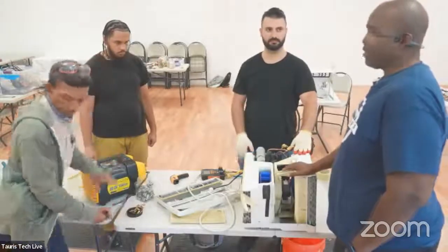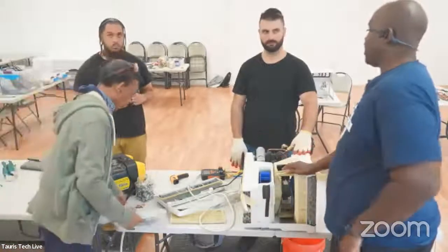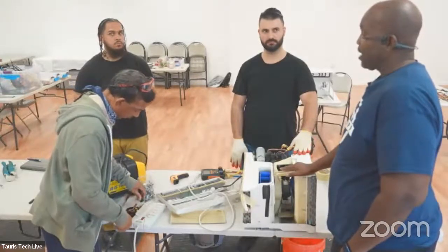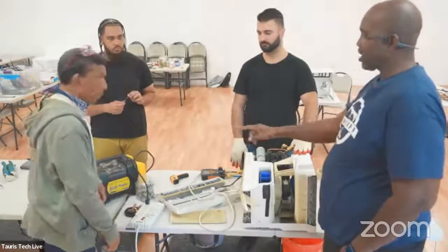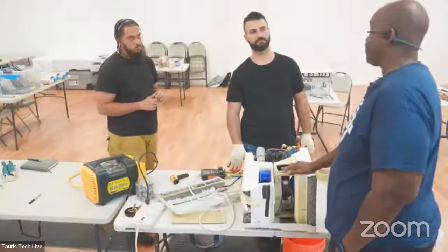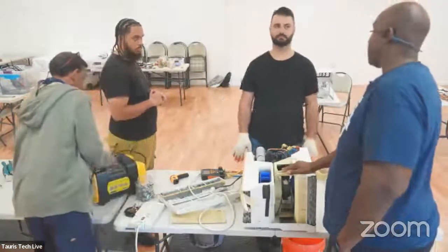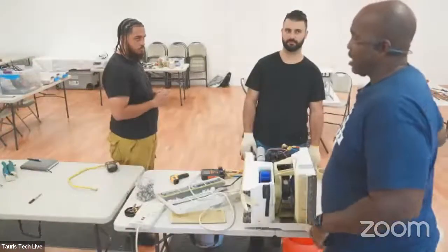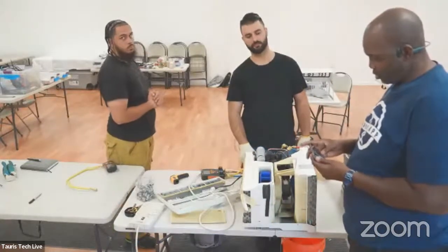Well, if I get one of the new tanks, it'll tell you on the tank itself. But any refrigerant that is a blend, how do you know a refrigerant is a blend? If you look at the numbers, we're not recovering, that's for recovery, we're just going to charge. Any refrigerant that starts with a 4 or a 5 is a blend. So 410A, 407C, 404A, 502, all of those are blends, and they all need to be charged as liquids.